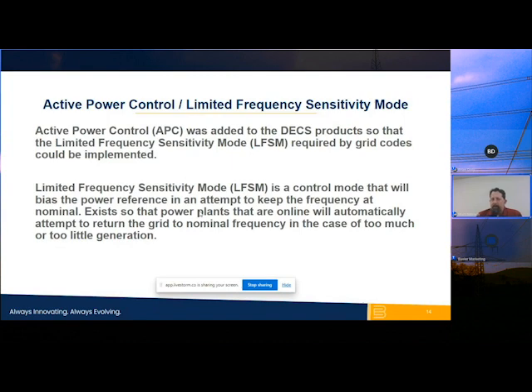What limited frequency sensitivity mode is, basically, is a set point change where the DECS is looking at the frequency, and as the frequency or the speed increases or decreases, we're going to set limits. We're going to start to decrease the amount of that frequency adjustment and create a bias. Now, the DECS products themselves are not governor controls. They don't control the frequency directly. What we do is monitor the frequency and monitor that grid connection.